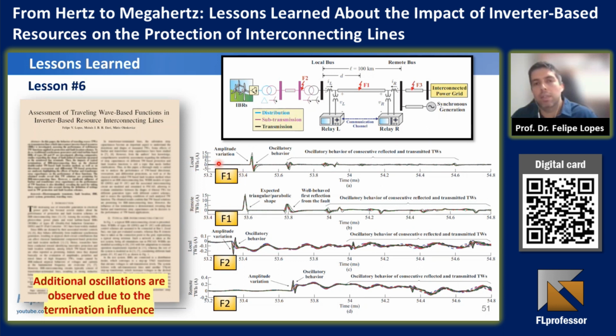We can see that on the IBR side there is some additional oscillatory behavior in the differentiated multi-filter outputs due to the transformer characteristic, but at the grid terminal, the expected triangular or parabolic shape output is obtained. But there is an interesting behavior here, because as soon as the reflections reach the IBR and go back to the remote terminal, they start to distort also the reflection. So detecting reflection here is very difficult. These signals here are related to the fault point F1, which is an external fault.